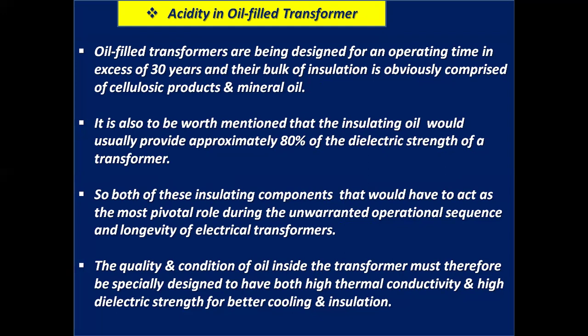Most important, both of these insulating components play the most pivotal role during the operational sequence and longevity of electrical transformers. The quality and condition of oil inside the transformer must therefore be specially designed to have both high thermal conductivity and high dielectric strength for better cooling and insulation.